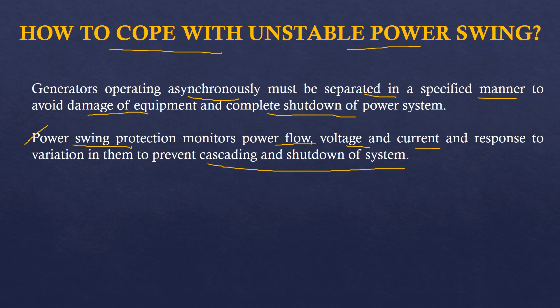Also, an out of step protection relay is used which avoids the tripping of any power relay during stable power swing. Since in stable power swing we have already achieved a new equilibrium position for the rotor angle, there is no need of tripping the generator, and hence the tripping should be avoided in case of stable power swing. But in case of unstable power swing, the system must be protected, and therefore this out of step protection relay differentiates between the stable power swing and the unstable power swing and operates accordingly, whether to trip or not to trip.